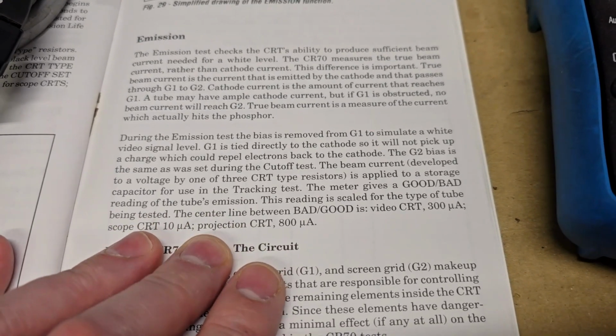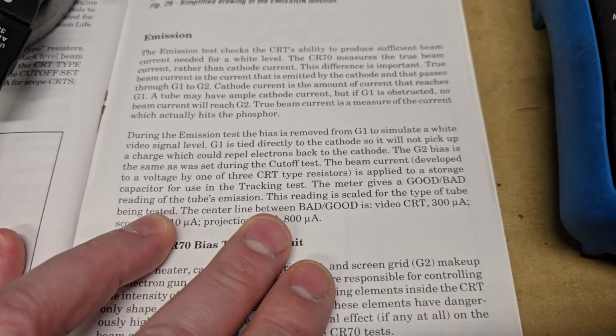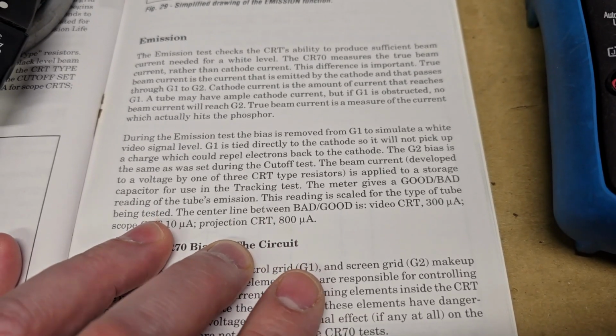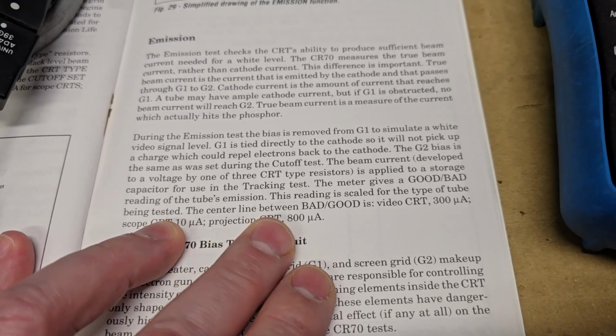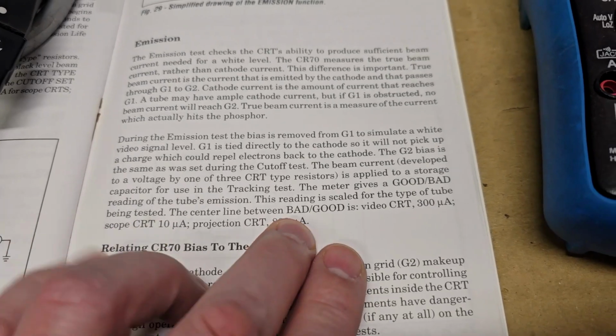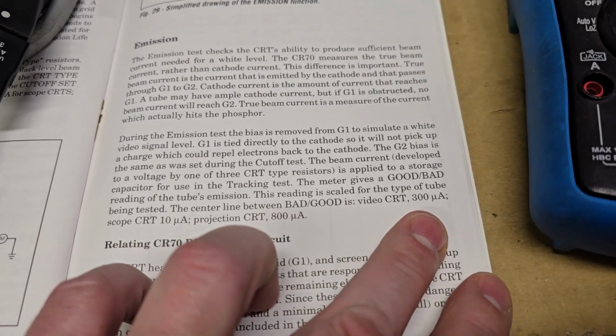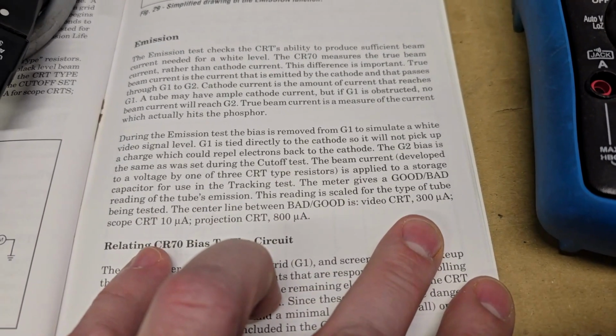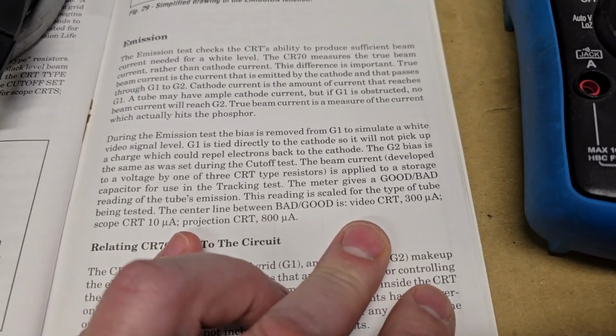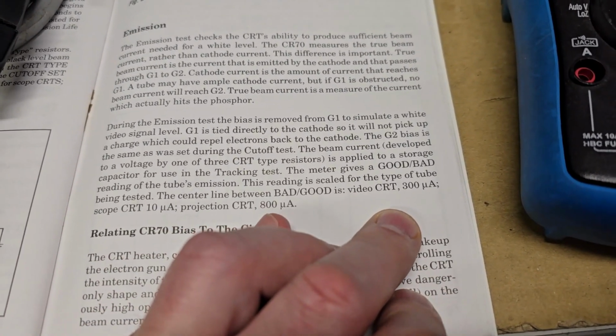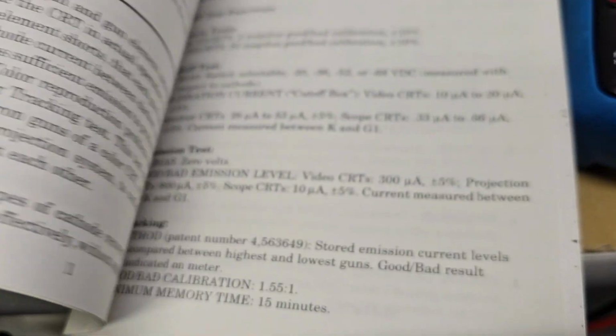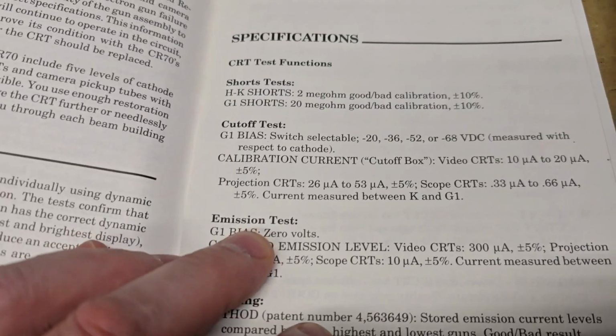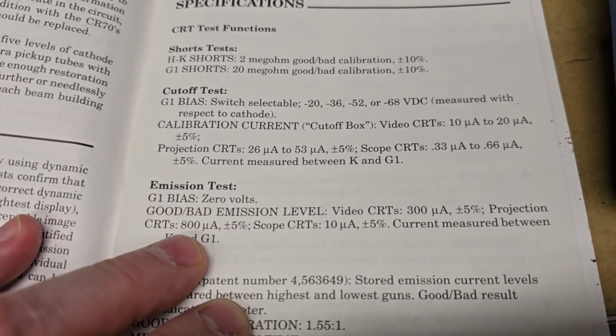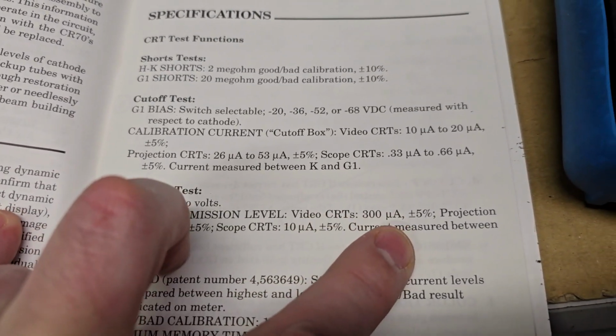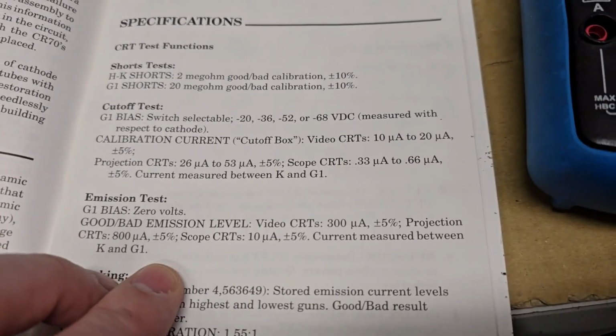Let's see. The meter is a good, bad reading of the tube's emission. This reading is scaled for the type of tube being tested. The center line between bad and good is video CRT 300 microamps, scope CRT 10 microamps, and a projection CRT 800 microamps.